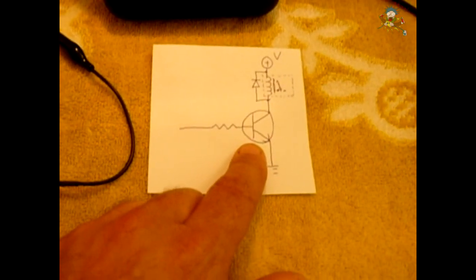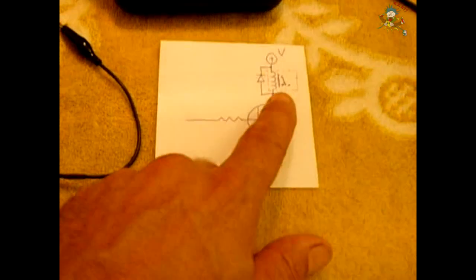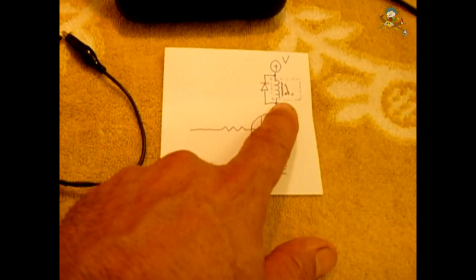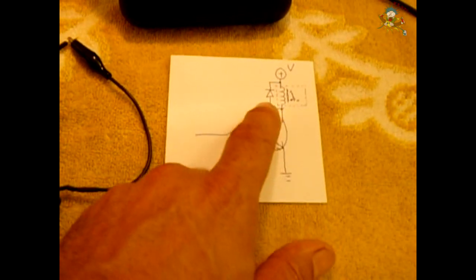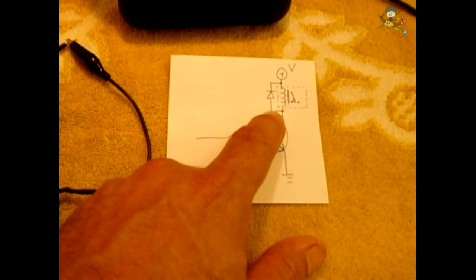Generally you will see a relay coil like you see here and in parallel with the relay coil you will find a diode hooked up reverse biased. That's there to protect against the collapsing magnetic field once power is removed from this relay.